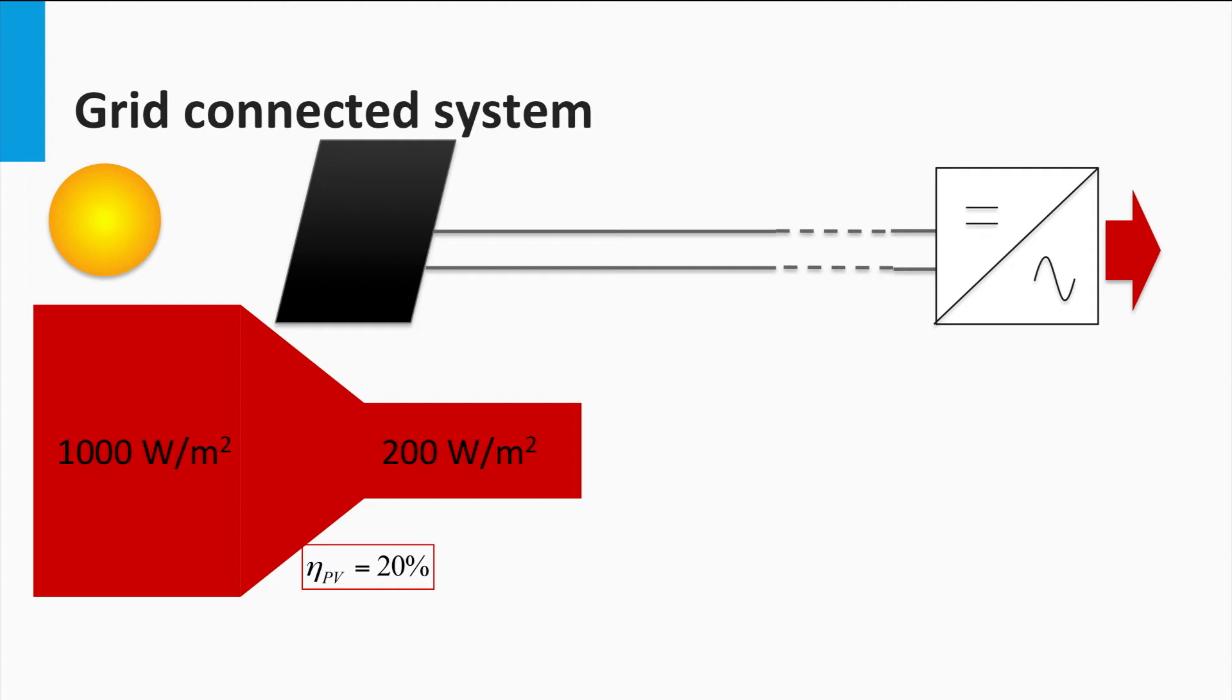In this example, let's assume that we have a cable loss equal to 2% of the PV power production, or equivalently the cables have a transmission efficiency of 98%. Therefore, the DC power per area going to the inverters is 98% of 200, which is 196 watts per square meter.